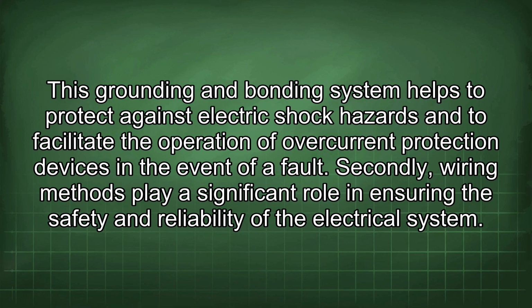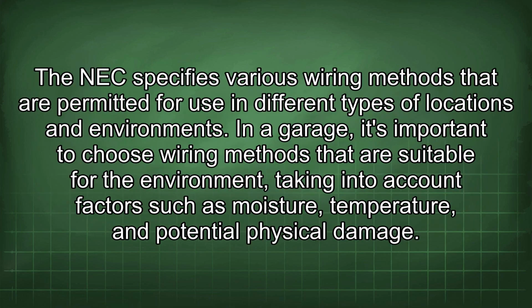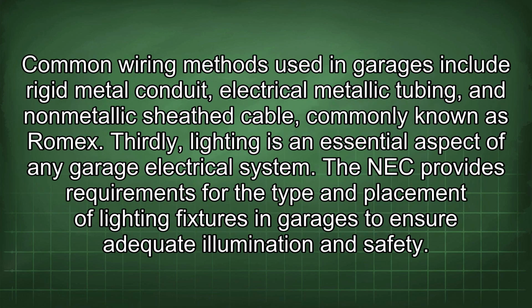Secondly, wiring methods play a significant role in ensuring the safety and reliability of the electrical system. The NEC specifies various wiring methods that are permitted for use in different types of locations and environments. In a garage, it's important to choose wiring methods that are suitable for the environment, taking into account factors such as moisture, temperature, and potential physical damage. Common wiring methods used in garages include rigid metal conduit, electrical metallic tubing, and non-metallic sheath cable, commonly known as Romex.